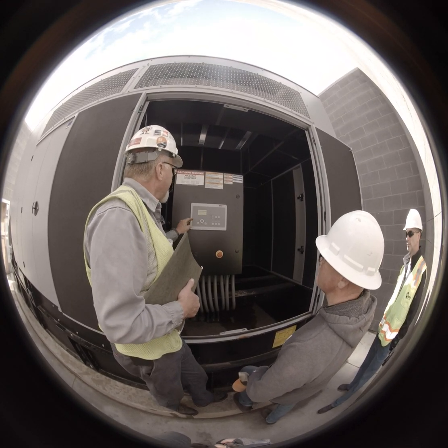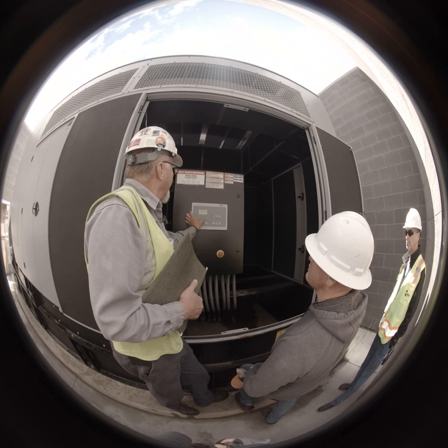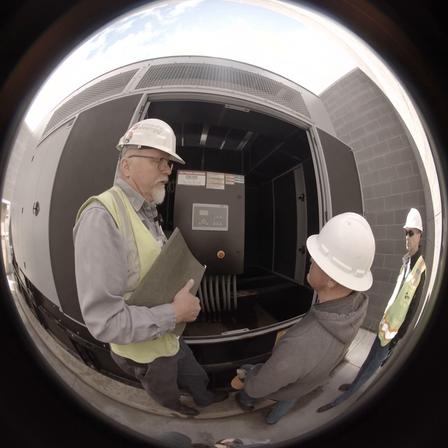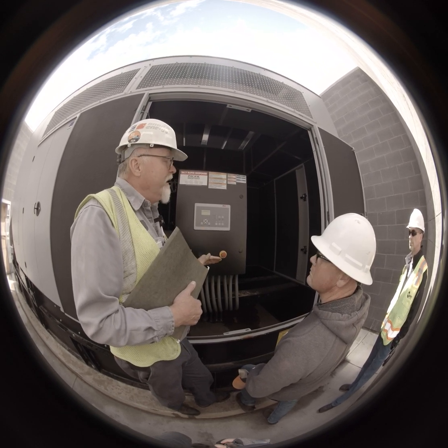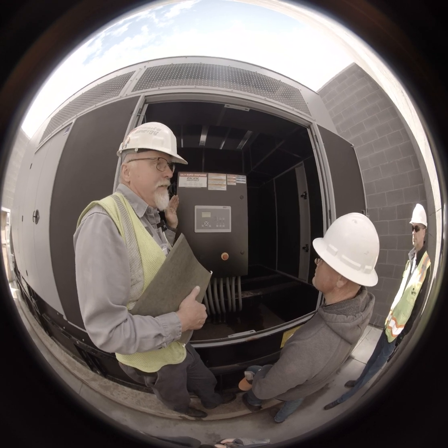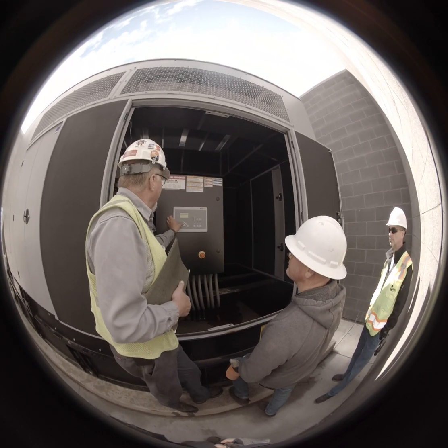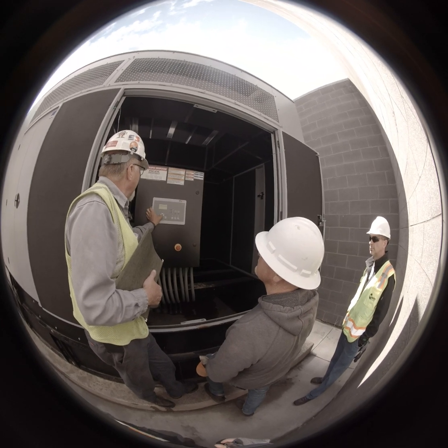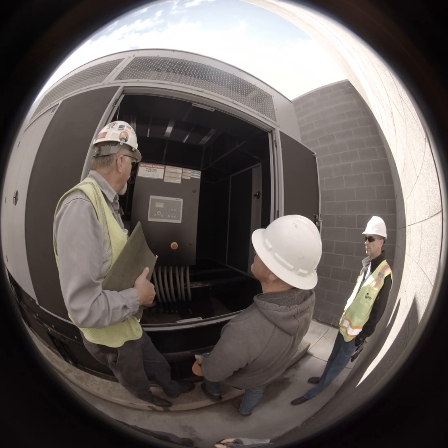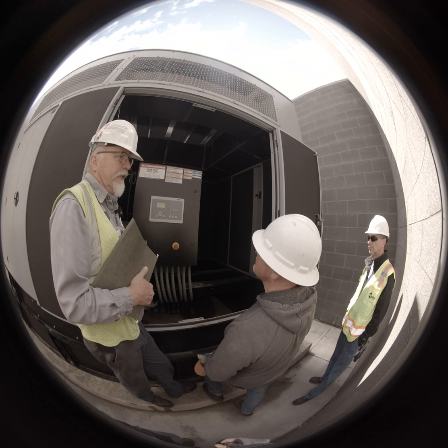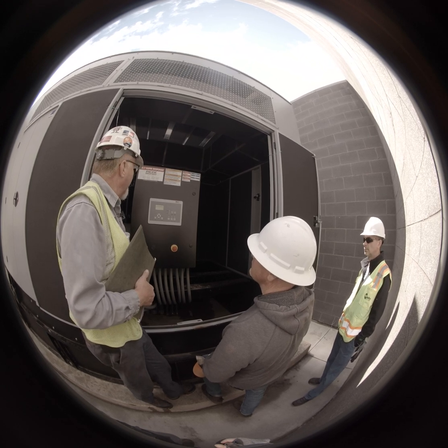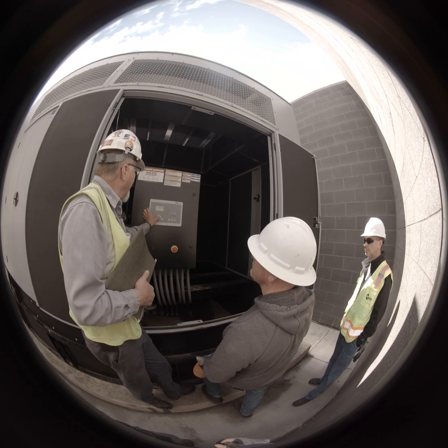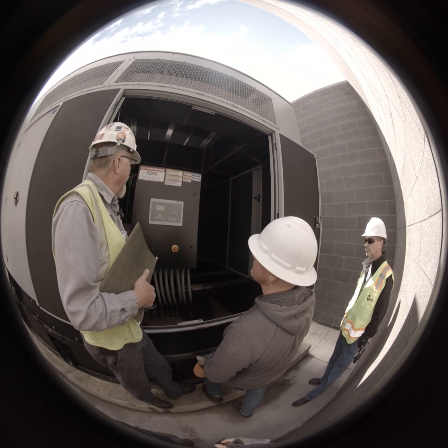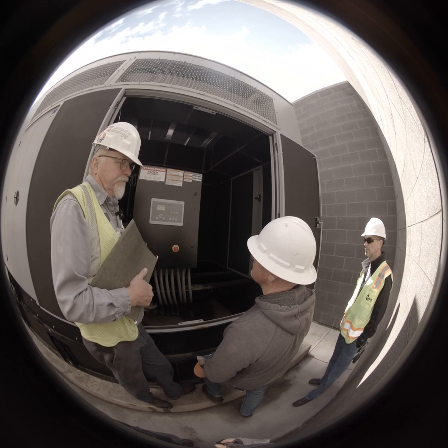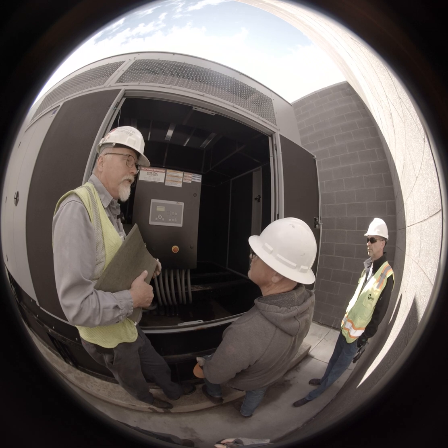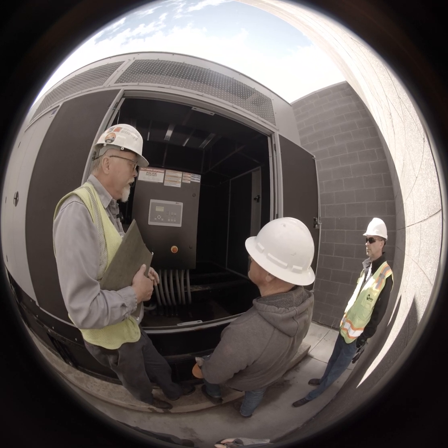Okay? So you go down and the total runtime is 5 hours and 40 minutes. This does not do tenths on this screen. It's in minutes. Okay. So the loaded runtime is 4 hours and 20 minutes. That was me. I did a 4-hour load bank test on it. Unloaded runtime, 1 hour and 15 minutes. All this stuff here you can report for EPA.